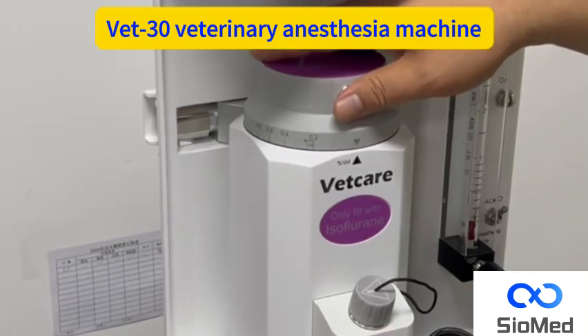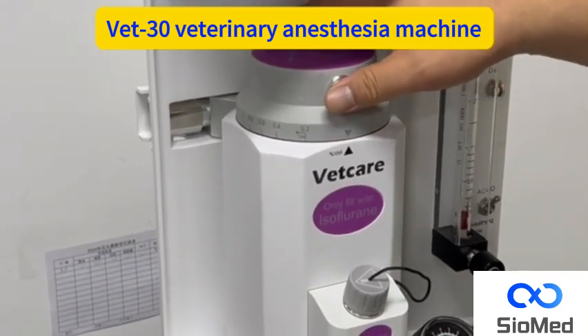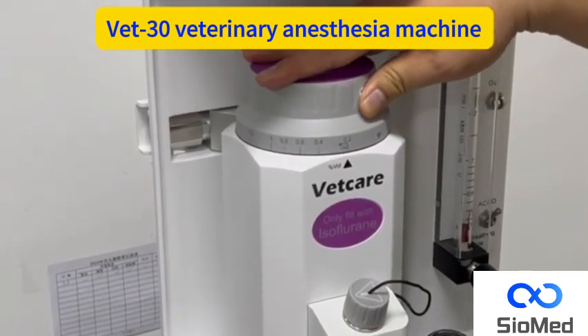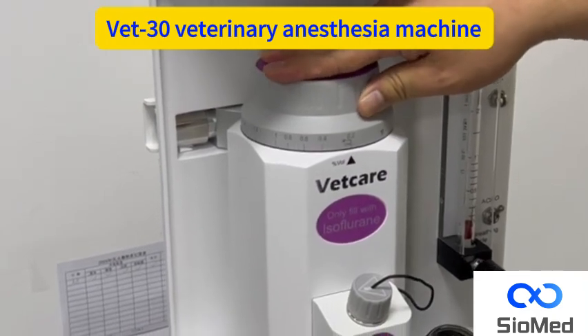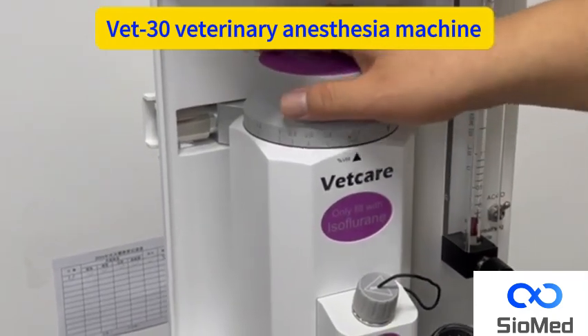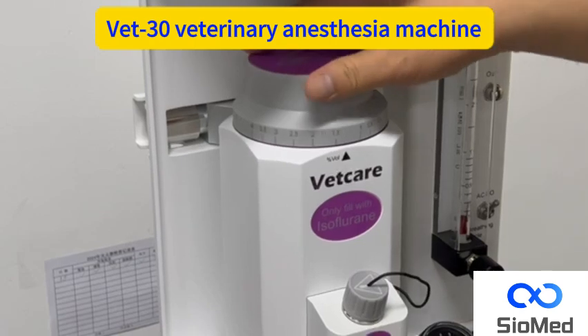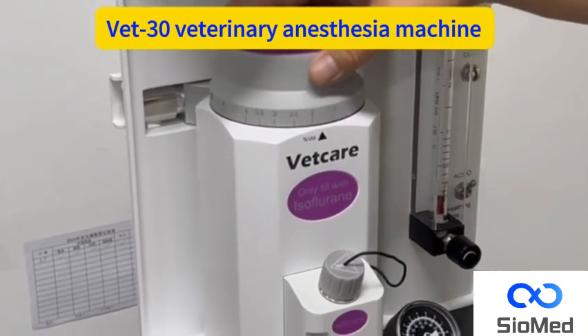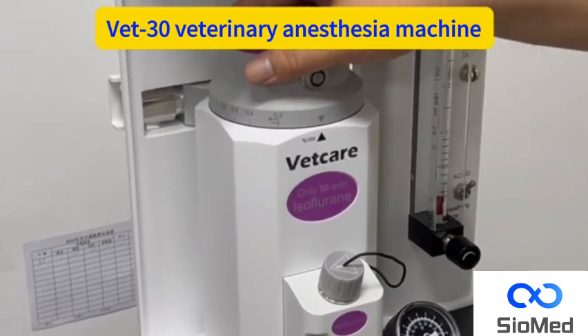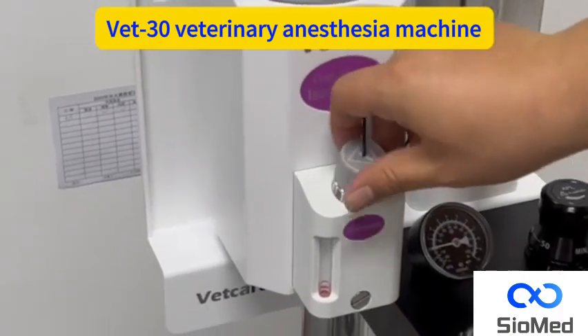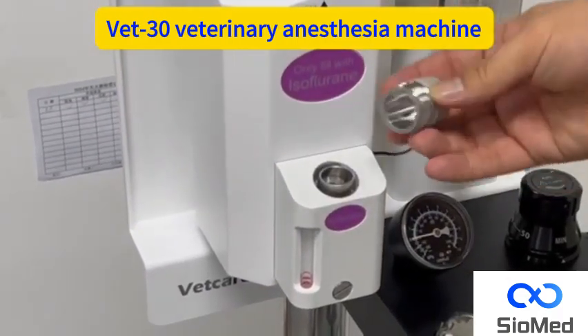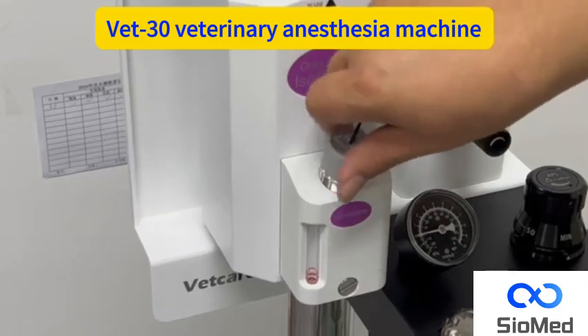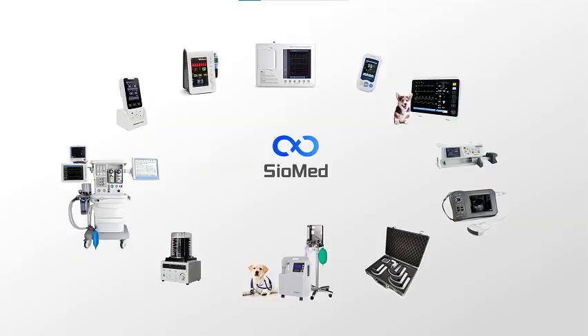To adjust the concentration of the vaporizer, we need to hold here down and rotate it. Its concentration ranges from 0.2 to 6. And a click indicates a reset. This is a pour fill. If a quick fill or key fill is required, it can be replaced. Above is a demonstration of the Vet30 veterinary anesthesia machine.